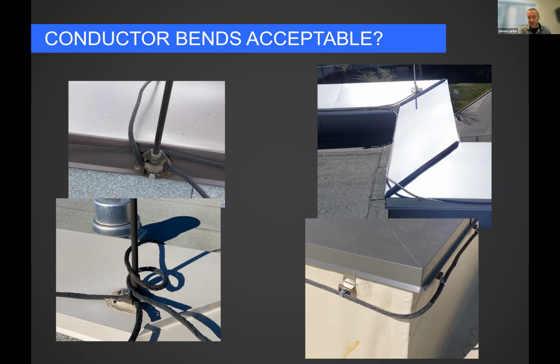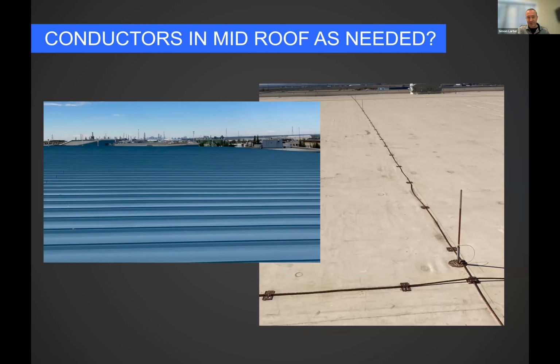That adds too much resistance to our cable. We want to make sure it's a gentle sweep. Mid-roof conductors, are they installed? On the right-hand side, yes, they are. There are our air terminals in the 15-meter grid in the mid-roof. You can see those mid-roof conductors go at 15-meter intervals.